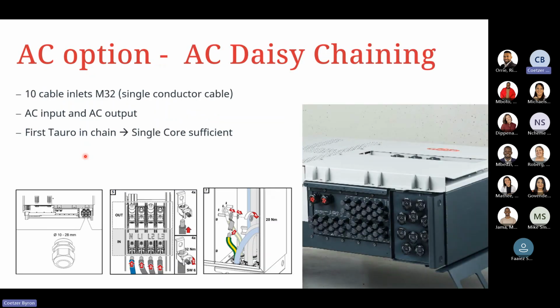Lastly, on the AC side, is a feature that's very handy for the Tauros itself, what we call AC daisy chaining. You'll have 10 cable inlets, M32 single conductor cable. It's an AC input and output on the AC side. For the first Taro in the chain, a single core is sufficient, whereas the last one will have the AC daisy chaining option, for example.